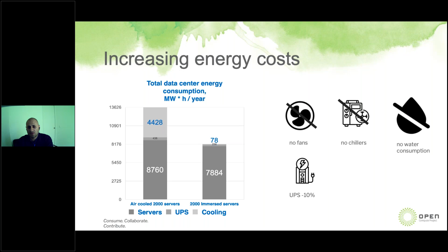And there are much fewer components that consume energy, and a higher temperature of the coolant, and it explains why our system uses 20 times less energy for heat transfer. Water is used only in extremely hot climates, and usage is decreased by 95%. UPS energy consumption also goes down due to lower IT load.